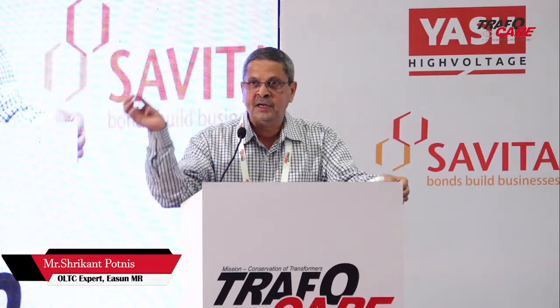Who is the manufacturer? If the manufacturer's design is already obsolete and the manufacturer doesn't exist anymore, then you can contact us, no problem, we also undertake repair work. In some cases it happens that the design is not at all compatible with ours, it's totally different. In that case we have to do retrofitting, we take out that OLTC and fit ours at that place. Okay, thank you sir.